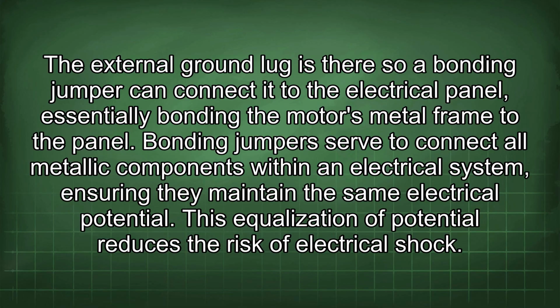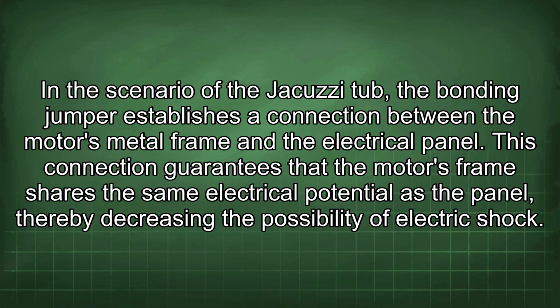Bonding jumpers serve to connect all metallic components within an electrical system, ensuring they maintain the same electrical potential. This equalization of potential reduces the risk of electrical shock. In the scenario of the Jacuzzi tub, the bonding jumper establishes a connection between the motor's metal frame and the electrical panel.